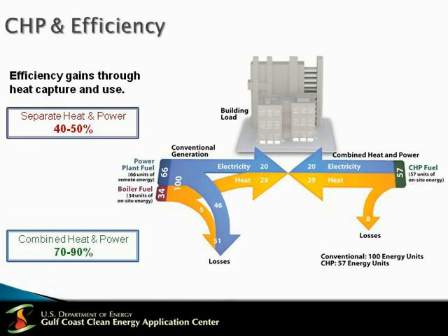The typical efficiencies for your conventional chiller, boiler, and separate heat and power is about 40 to 50% efficiency. And as we said before, combined heat and power basically has efficiencies in the 70 to 90% range.